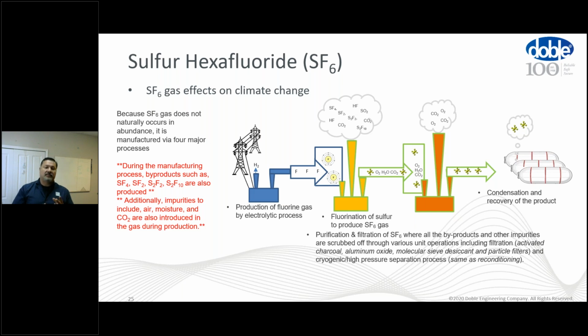Because SF6 does not naturally occur in abundance, there are some traces of it found, but obviously not to the level of what is needed. It's manufactured via 4 major processes. It's very important to note that during this manufacturing process, byproducts such as SF4, SF2, S2F2, and S2F10 are also produced. Other impurities like moisture, CO2, and air are also introduced to the gas, and all this needs to be scrubbed out. The process works like you see here throughout this illustration. Through an electrolytic process, we produce the fluorine gas, much like Henry Moissan did in his work. We introduce the fluorine and the sulfur to produce SF6 gas, and at this point, we're creating a number of those byproducts as a result.